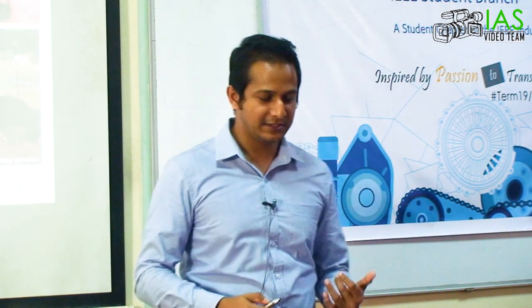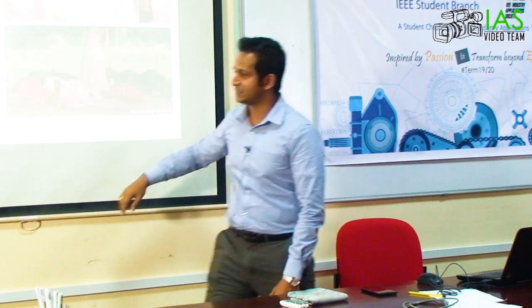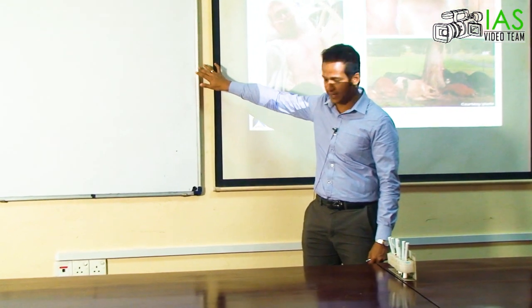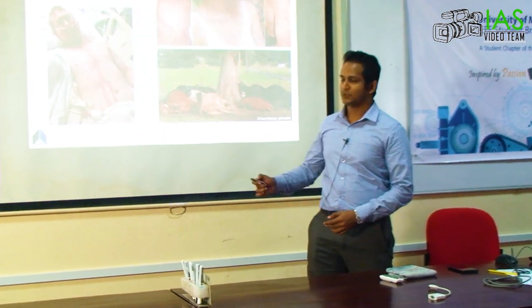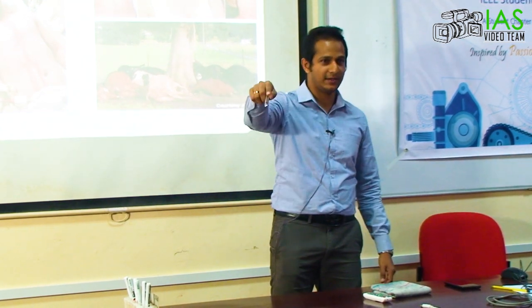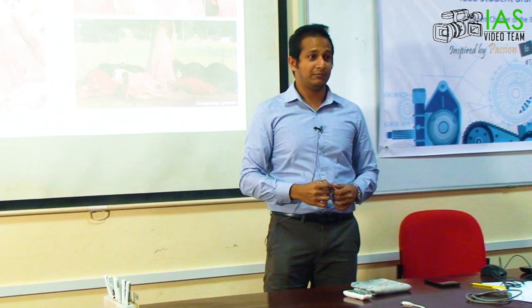Step potential is simply the voltage difference applied across my legs. Touch potential is when I'm touching, say, a metallic surface, and a voltage applies between my hand and my feet. If that exceeds my breakdown voltage, then I'm dusted. Although I'm standing here without touching anything, if lightning struck somewhere around here, once the voltage profile is built up, the voltage difference that applies between my feet would determine my life expectancy, maybe.